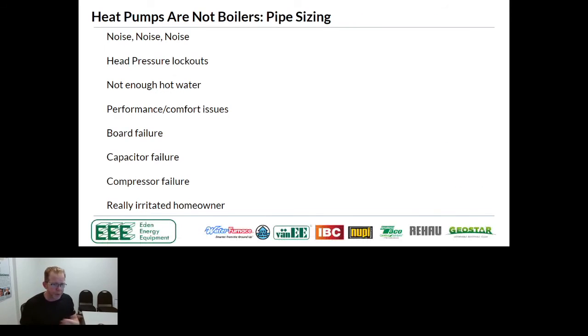So sort of wrapping everything up as we go through it, key things to look out for is that if you're doing something wrong with your heat pump, you're going to know pretty quickly. Whether it's air to water or water to water, if it's noisy, there's a reason for it. It's kind of like your car. I know absolutely nothing about cars, but if my tires start making a weird noise, it's like, oh, that's not normal. I should probably do something about that. You'll end up with head pressure lockouts. You'll have customers complain and say, I don't know why the unit runs for a few minutes. It sounds really, really loud, and then it shuts off.